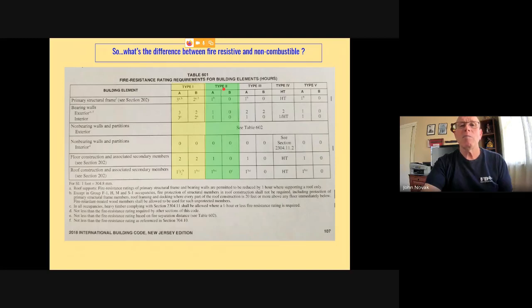With non-combustible type A, you have 1 hour fire resistance ratings of some of the structural members. Type B is the construction that we were concerned with in non-combustible because of direct flame impingement on structural steel members and having collapse relatively quickly. There is no fire resistance. It's all zero. So that's the difference between fire resistive and non-combustible.